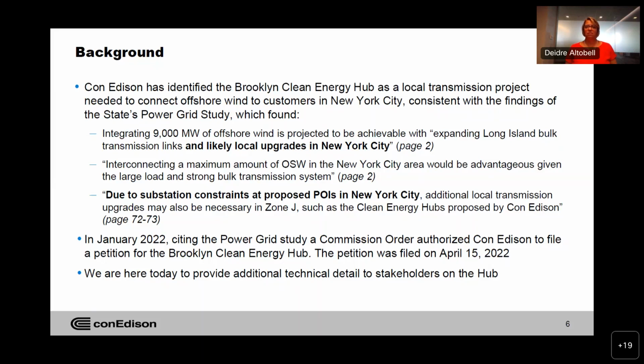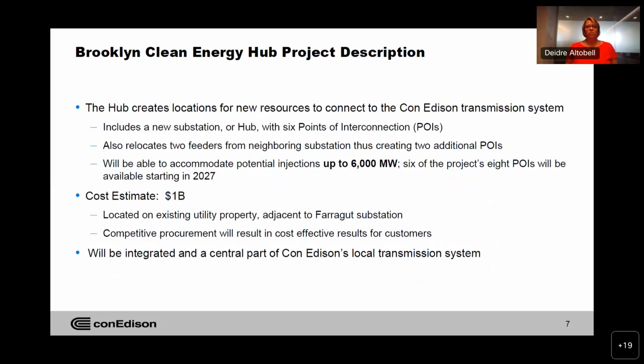What is the Brooklyn Clean Energy Hub project? It is a substation project with a primary objective to create new points of interconnection on the Con Edison system for large resources such as offshore wind. It includes a new substation, the Brooklyn Hub, with 6 new points of interconnection, or POIs. Additionally, the project will relocate 2 feeders from a neighboring substation, Farragut, which in turn will open up 2 bus positions for additional points of interconnection at that substation. When completed, the hub project will enable a total of 8 new points of interconnection, or POIs, that can support the injection of up to 6,000 megawatts.